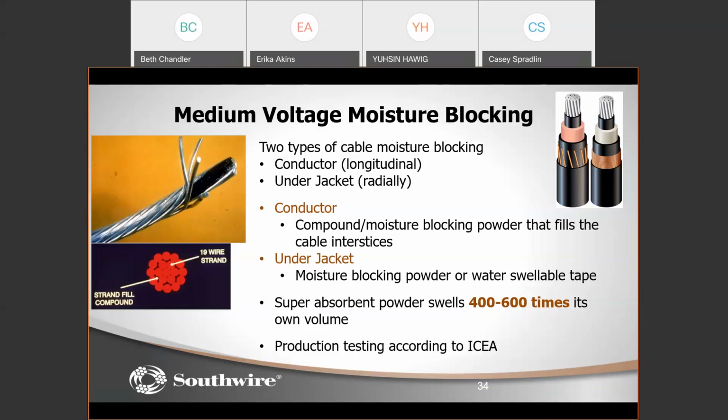You pump this compound in, and then you dust that compound with this super absorbent powder that we talked about, and that combination, called a moisture block conductor, will prevent any moisture from traveling up and down the cable in the event that the conductor is exposed, either via a termination leaking or splice leaking, or in the event you have a failure in a direct burial system, and you want to splice the failure point right there and keep the remaining cable. You don't have to worry about any moisture getting inside the conductor and causing any long-term damage.